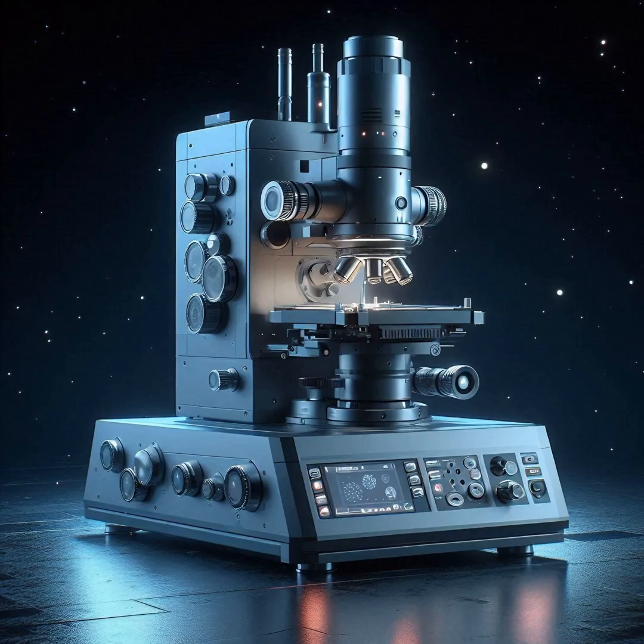Many types of imaging are common to both TEM and STEM, but some, such as annular dark field imaging and other analytical techniques, are much easier to perform with higher spatial resolutions in a STEM instrument. One drawback is that image data is acquired in serial rather than in parallel fashion.